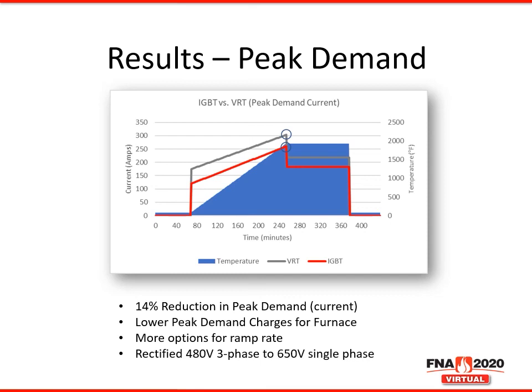This also offers the furnace operator the ability to change the ramp rate. The furnace can get up to heat faster for that same peak demand, making the furnace more productive. Or, conversely, the operator can focus on peak demand and reduce that throughout the facility. The reason why we see a lower peak demand is that the control, which I'll get into later, rectifies the three-phase 480 volts upstream to 650 volts out of the control. This higher starting voltage allows us to step down the voltage further within the transformer, which results in a lower primary current draw throughout the entire system.